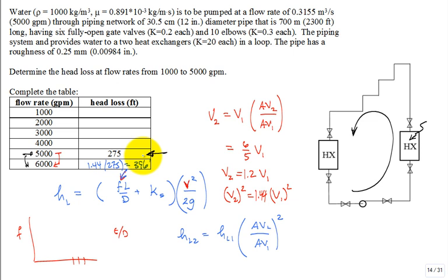How about if you went to 4,000? You calculate that? You're dropping now this time, right? So it'd be 0.8 quantity squared times 275, be 176. That's like a significant drop.